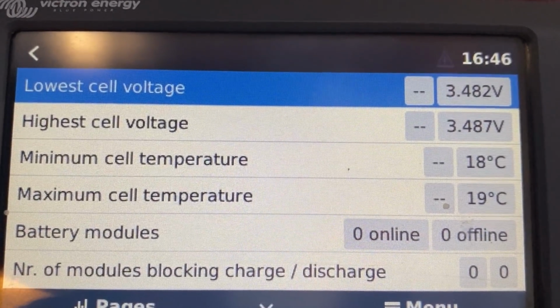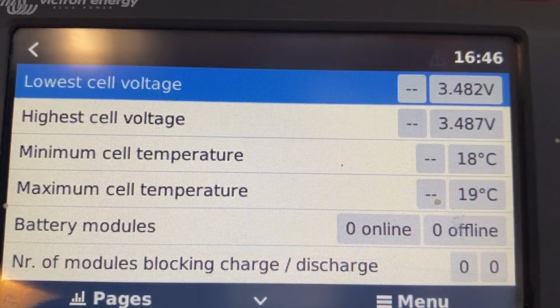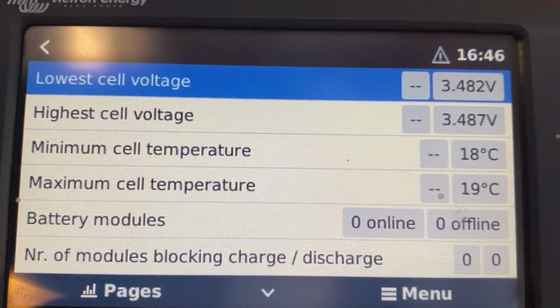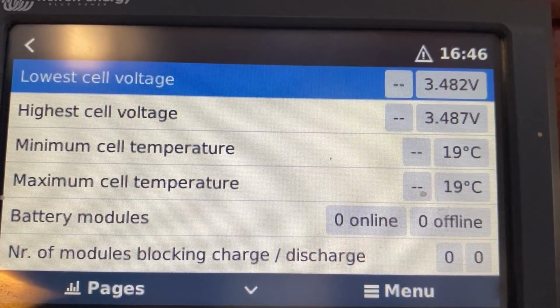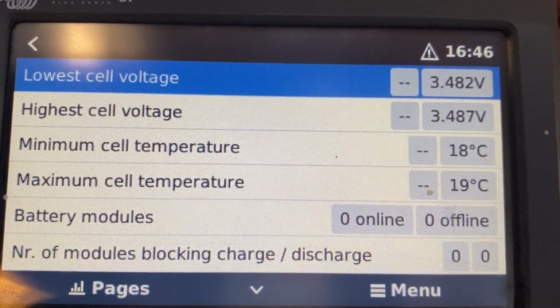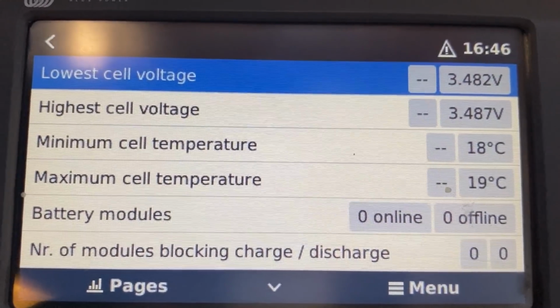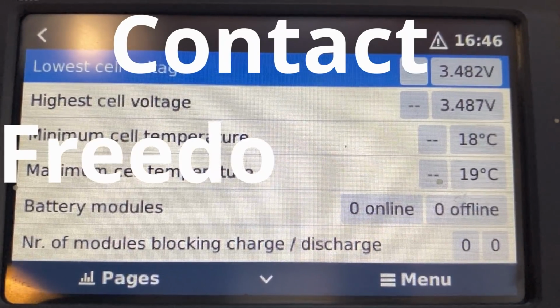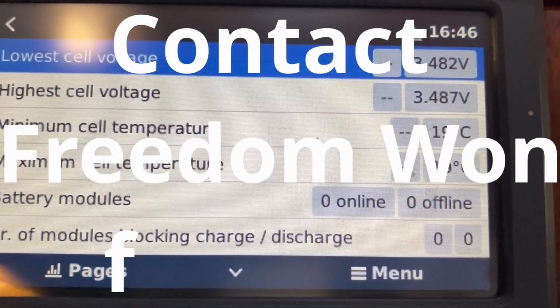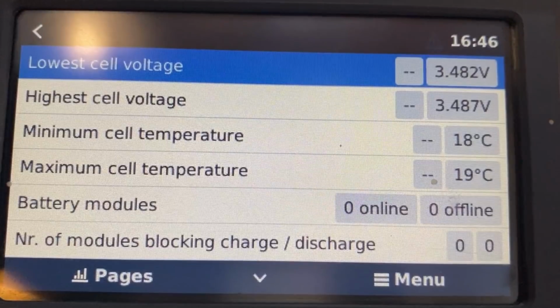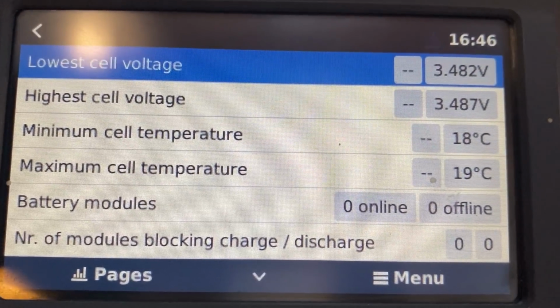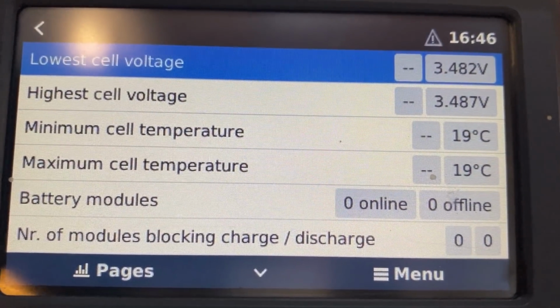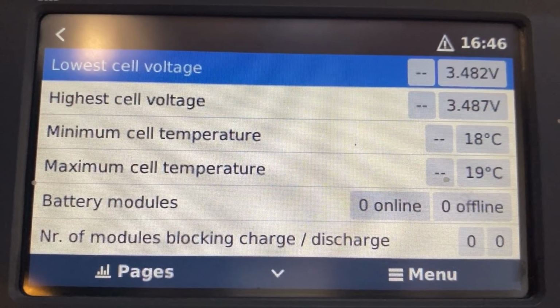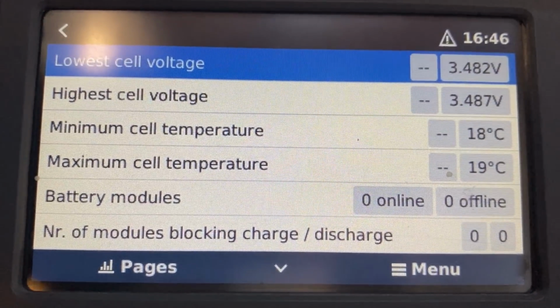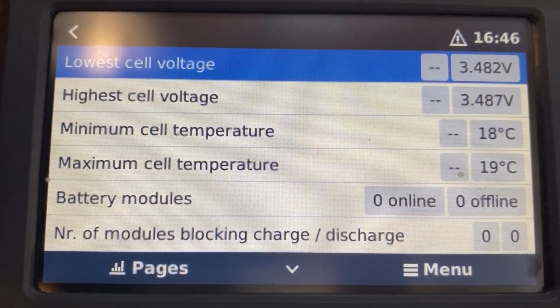So you always want to make sure your lowest cell voltage and your highest cell voltage are very close. Basically 0.02 of a difference or more is probably significant enough to worry about. The difference between 3.482 and 3.487 is 0.005, very small. So it's important to look at this every so often.